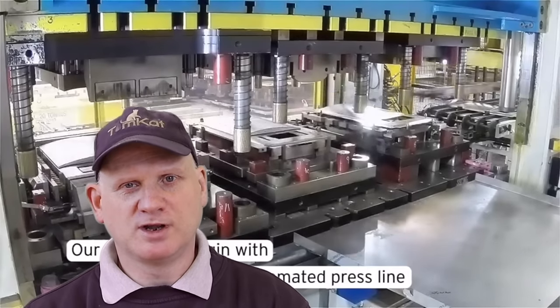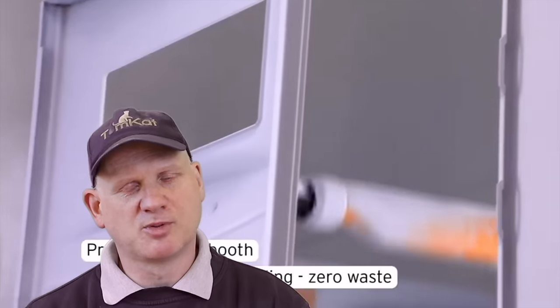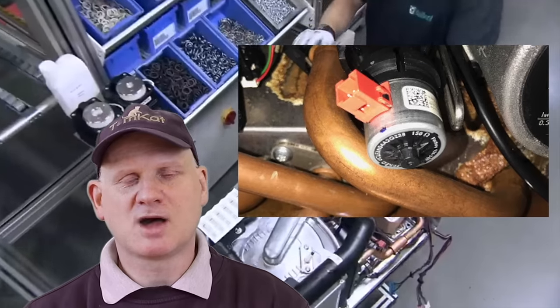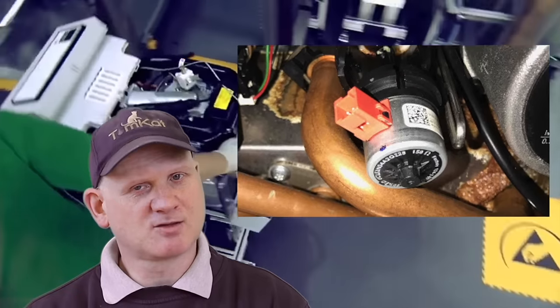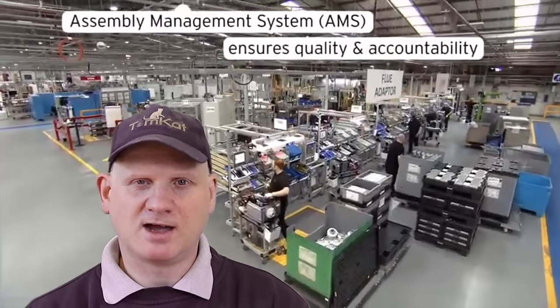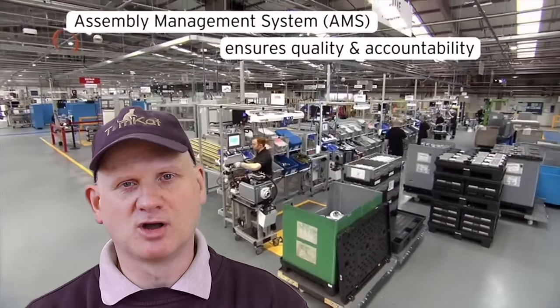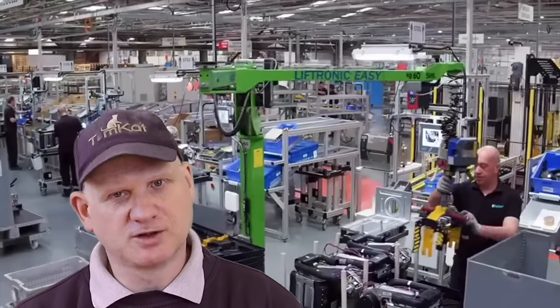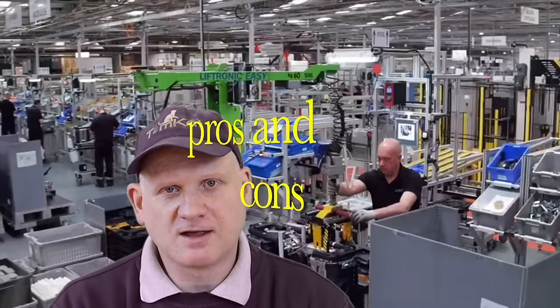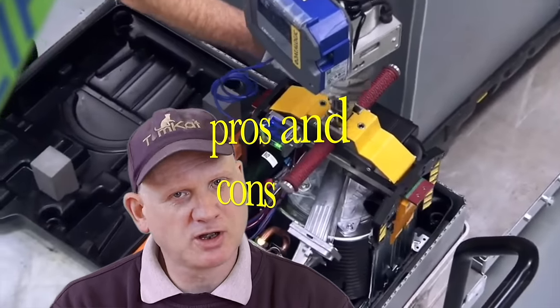The main issue with the Vaillant ecoTEC range of boilers, first, they are very expensive to purchase, and second, spare parts are also incredibly expensive. The biggest problem we seem to find with the ecoTEC range of Vaillant boilers is faulty diverter valves. But again, this might not be a manufacturing issue, this might be an installation issue, where installers are installing brand new boilers on 30-year-old dirty systems. So let's look at the pros and cons of the Vaillant Group's boilers.